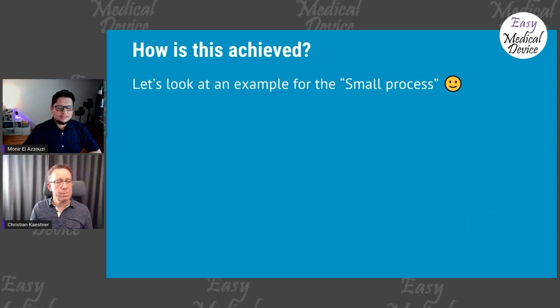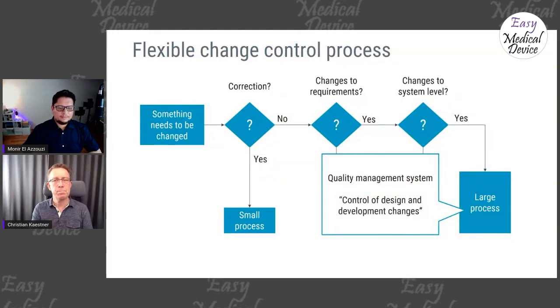And just maybe to come back on this one. Just to make a parallel with the MDR, remember we are actually in a transition period, from the 26th of May 2021 until the 26th of May 2024. It means that during this transition period, if you are following the MDD, which is Medical Device Directive, and you are a Class 1 device, Class 1 software, if you are making a significant change, then you will normally have to follow the MDR. This is mainly the requirements here.